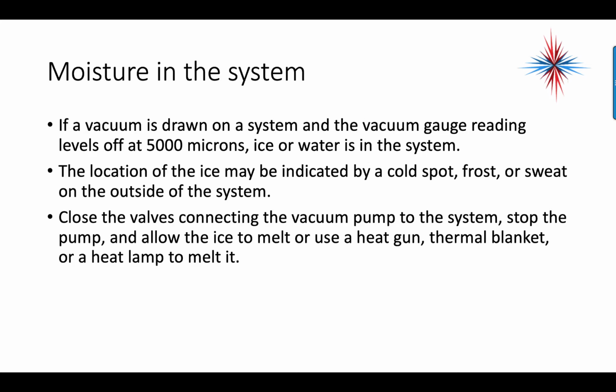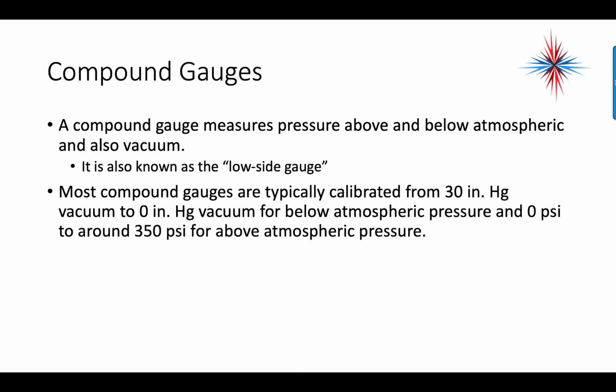So if a vacuum is drawn on the system and the vacuum gauge's reading levels off at 5,000 microns, there's still ice or water in the system. Remember, the lower number is a deeper vacuum. The location of the ice may be indicated by a cold spot, frost, or sweat on the outside of the system. Close the valves connecting the vacuum pump to the system, stop the pump, allow the ice to melt, or use a heat gun, thermal blanket, or heat lamp to melt it.